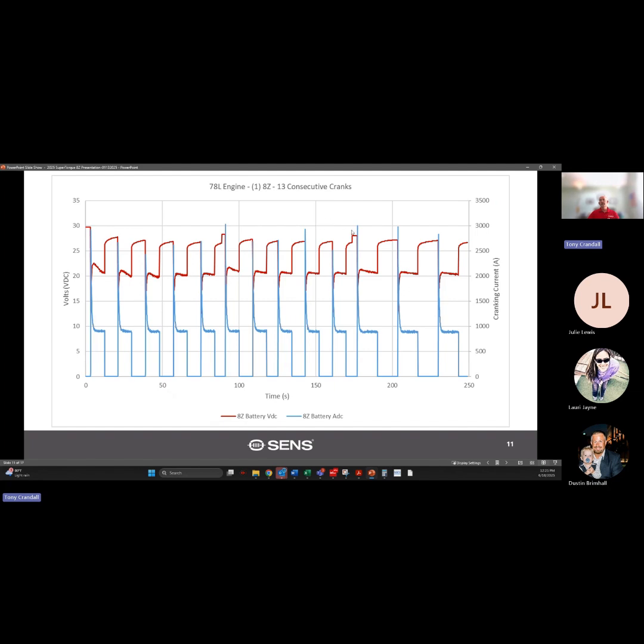What you see on screen during these first 10 cycles is a scenario where we were cranking the generator for 10 seconds and then waiting for an additional 10 - crank for 10, wait for 10, so on and so forth. Then we went into a more traditional NFPA 110 style sequence, where these last three cranking cycles were a 10-second crank, a 15-second crank, and a 15-second pause.